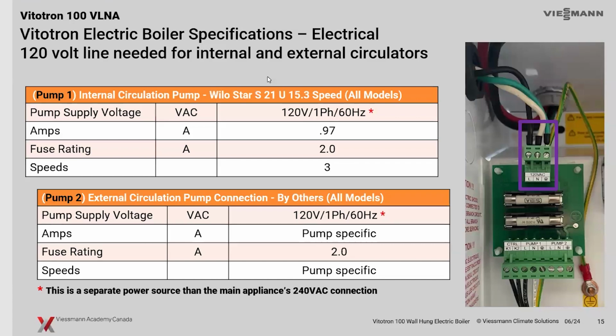And on the 120 volt side here, just again to review, there's a little bit of an up close and personal look at that connection on 120 to the neutral line and our ground. And then we've got our pump outputs here on the bottom. Now, there's actually 2 pump outputs. The main pump output for the built-in circulator on the boiler is already pre-wired in the factory. It's a little Wilo Star S21. So if you're familiar with the Wilo brand, as far as outputs, it's very similar to the Grundfos UPS 15-58s, some of your Taco 007, 010 type of pump. So residential style of pump.